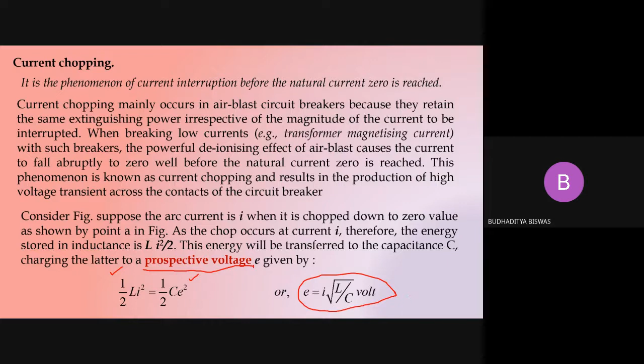So the prospective voltage E is very high as compared to the dielectric strength gained by the gap, so that the breaker restrikes. As the deionizing force is still in action, chopping occurs again. So there is multiple chopping of the current. Here you see in the figure also there are multiple choppings of the current, and in this figure four times the chopping occurs. This is the fourth time the current chopping occurs.